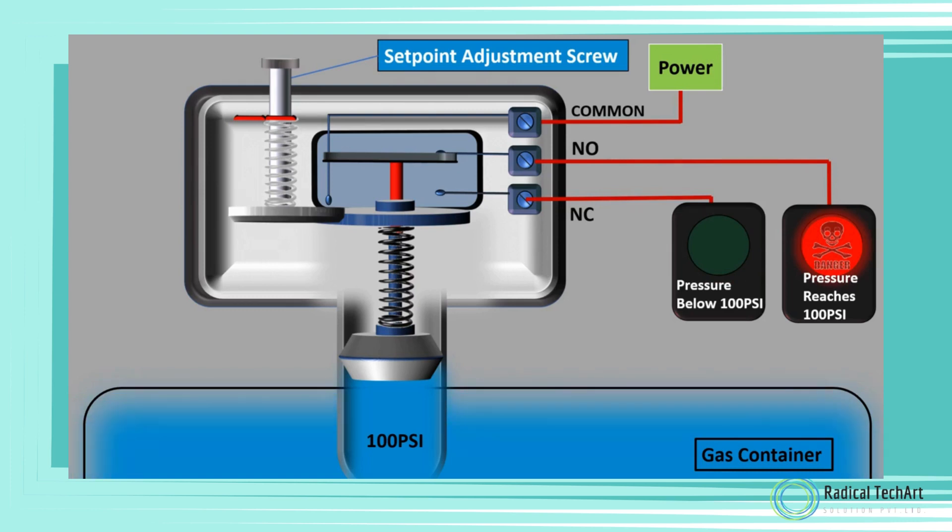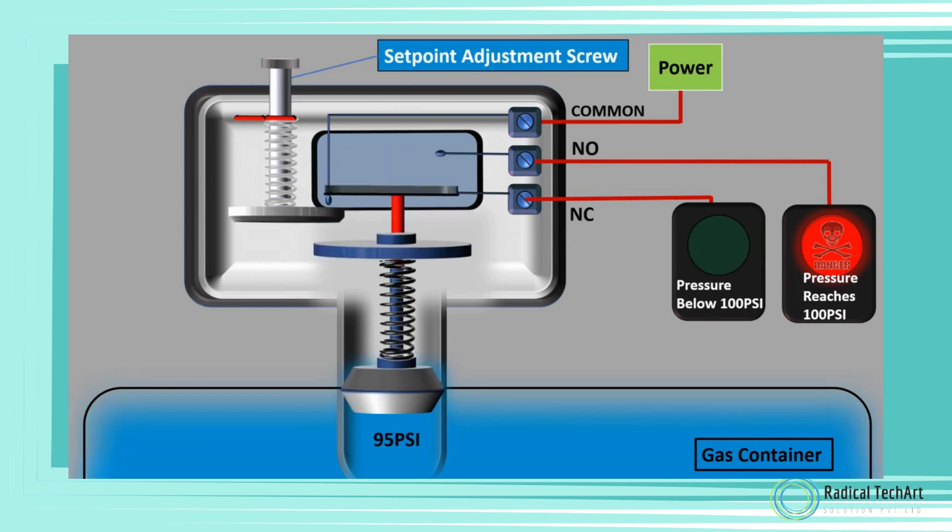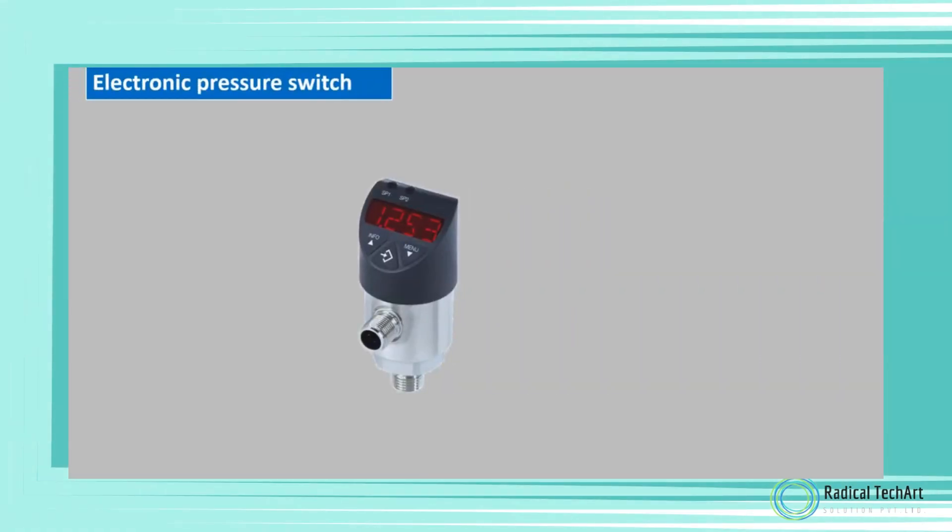If this pressure switch has a differential of 5 PSI, then reset pressure will be 95 PSI, which means that when the pressure reduces to 95 PSI, then the switch will come back to its normal state, that is green light will be on and red light will be switched off.